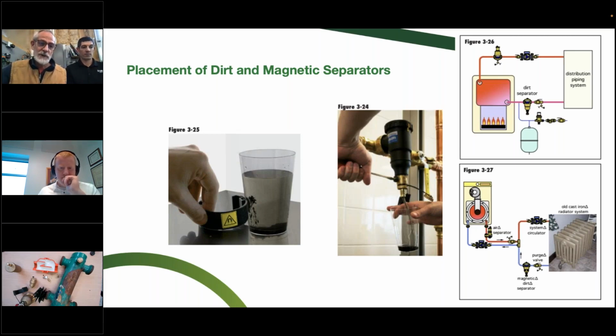So what you want to do is take a sample and let it settle out. If it attracts to a magnet, whatever you have for a magnet, it's magnetite. And it's going to keep happening if oxygen is getting in that system, or if you've got, on the lower right over there, a cast iron radiator that's been breaking down for 100 years and you put a new pump and a new system in there. It's cheap insurance for a system. Certainly if you're putting an ECM pump on, you should have a magnetic separator in the system.